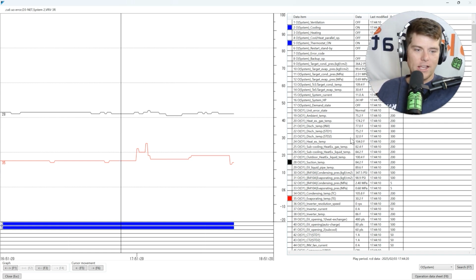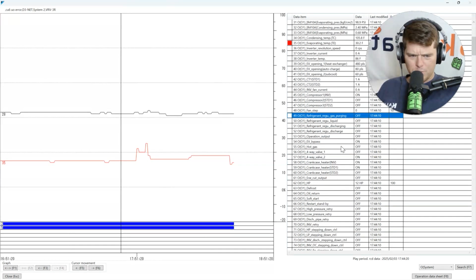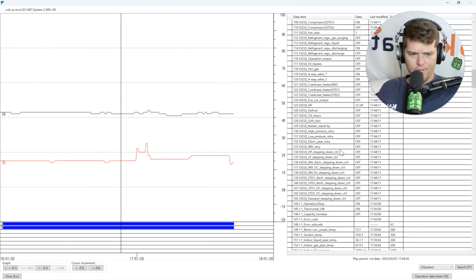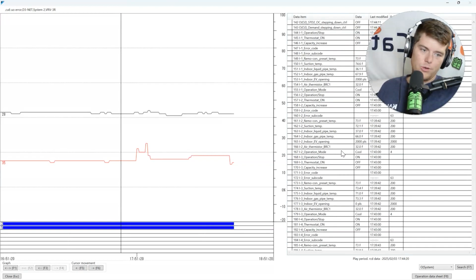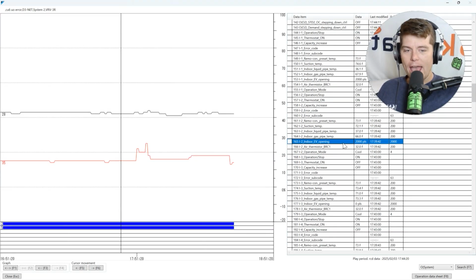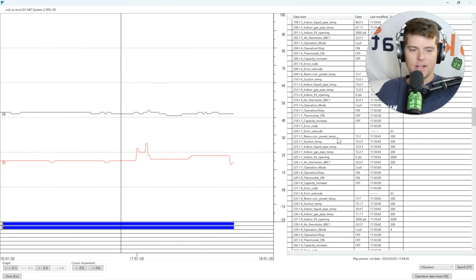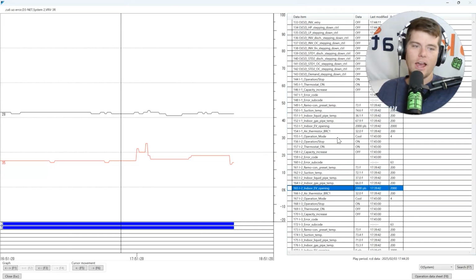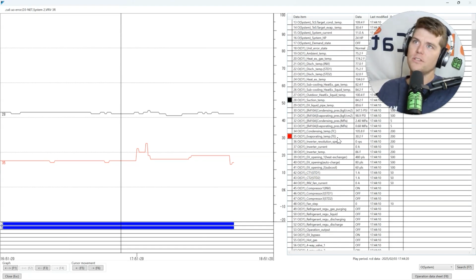Now, I can even go further if I want to, and here we can go further. Another key indication of undercharge on a system, 2,000 pulse valves, right? Wide open, not metering refrigerant. We've talked about this many, many times here. Valves that are wide open or all the way closed are problems. We're not getting enough gas to these indoor units. Now, everybody loves to go to the EEVs inside and say, yeah, 2,000 pulses. Yeah, 2,000 pulses means undercharge.